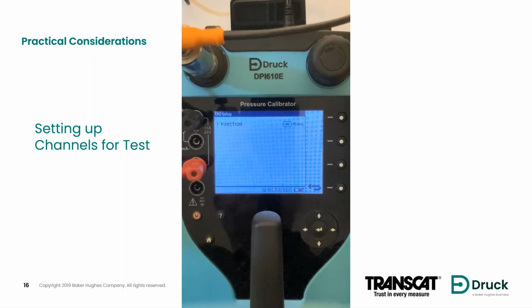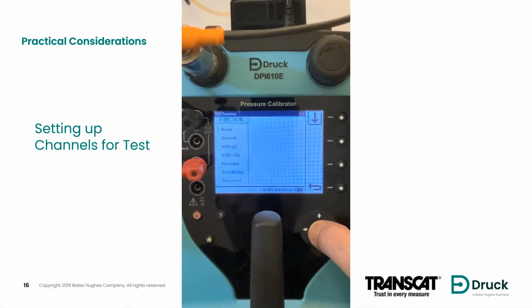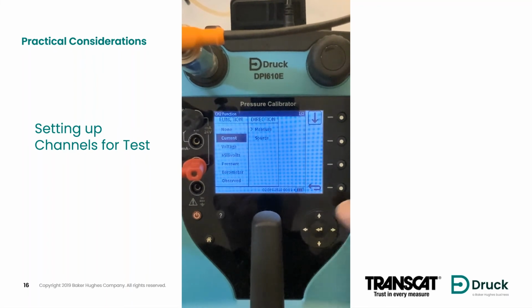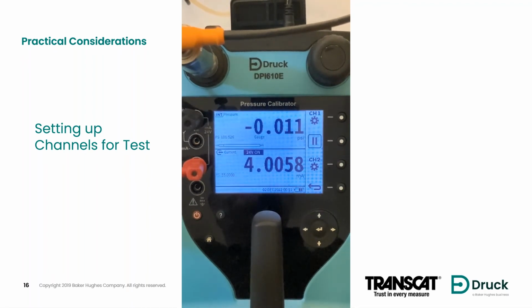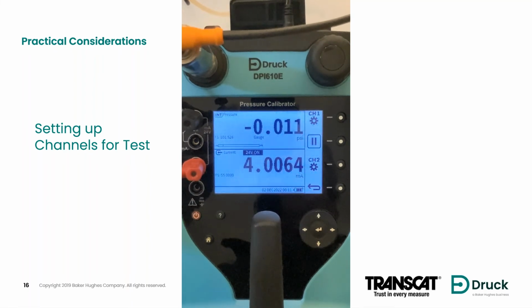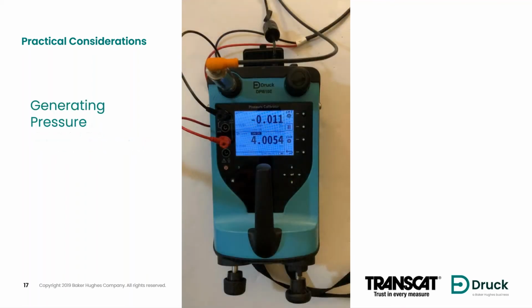I'm setting up the second channel, or channel 2, for the electrical functions. So I'm measuring current, and this is where I have the option to turn on the 24-volt power supply to energize the device under test. You'll see that there was also a 10-volt option there if you're doing a transducer rather than a 4 to 20 milliamp transmitter. So again, fairly simple, fairly intuitive to set up the channels for tests. Now we're ready to actually generate pressure.